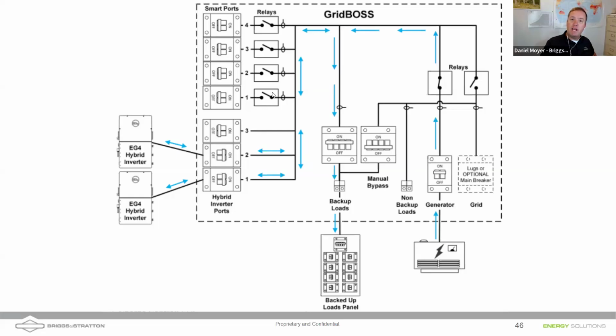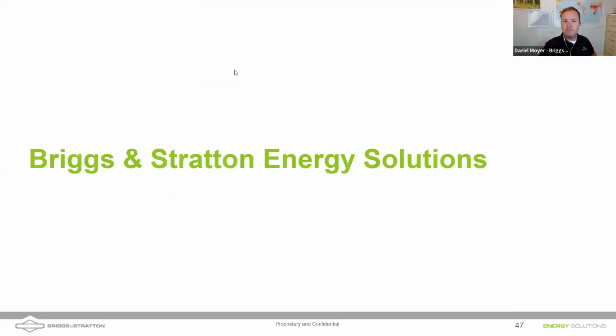But notice what happened over here, where that AC coupled PV was - that relay automatically opened up. That eliminated the need for us to have an external PSP product or an external Briggs & Stratton relay. It's built in. It also opened up all these smart ports, since these should be a lot of your luxury loads.